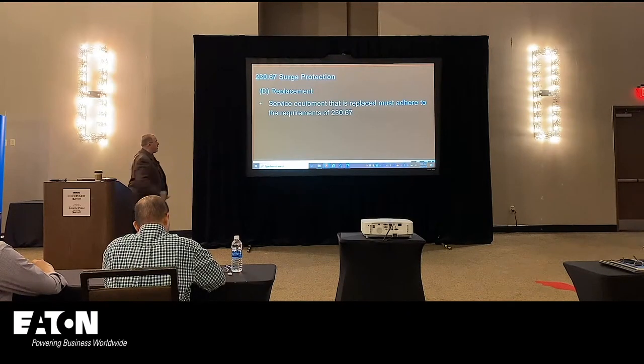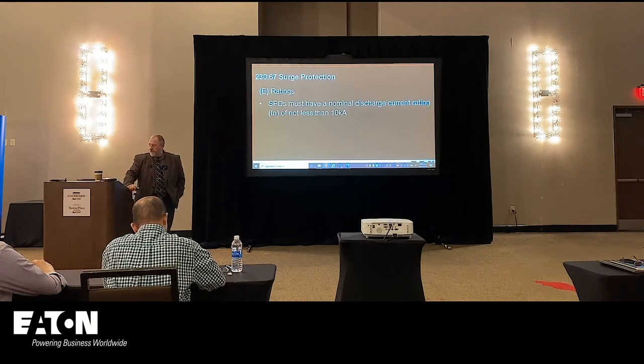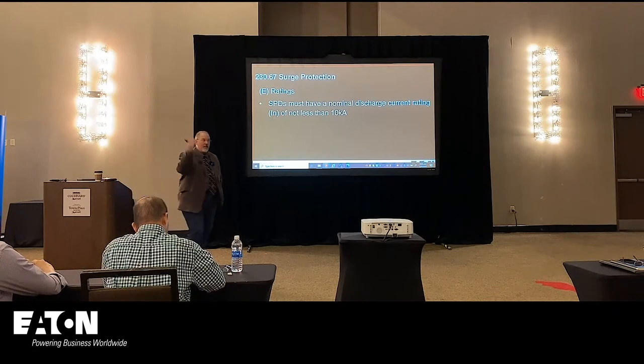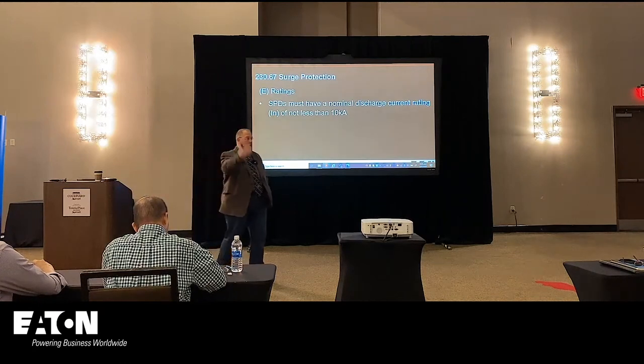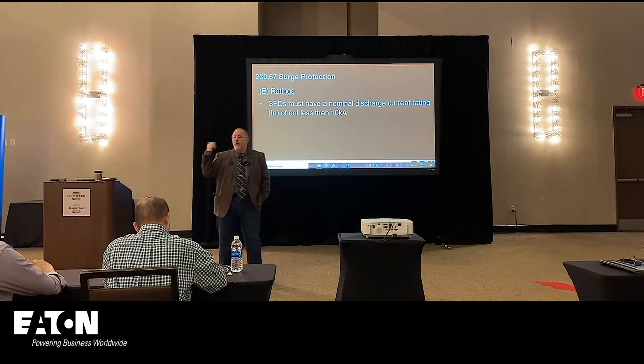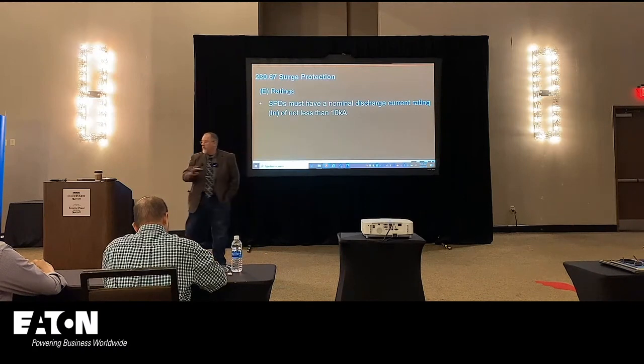There's your replacement. If you replace it, then you have to adhere to the requirements of 230.67. And we put this same language in 215 and 225 as well. I have a feeling that in the next cycle, we're going to clean up the rest of the surge locations as well. So this is just a taste of what's probably going to come for industrial control panels and Article 700 systems, et cetera. It's just a flavor for what you're probably going to see over there.